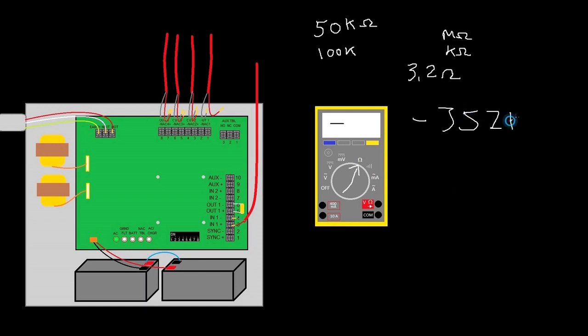Well, the negative is a dead giveaway that we have a problem. And to me, just from experience, I'm going to say the first thing I would check is, maybe you look at your panel and your threshold should be 100K from all the circuits and everything else is clear reading OLs. Well, why is that showing up ground fault?